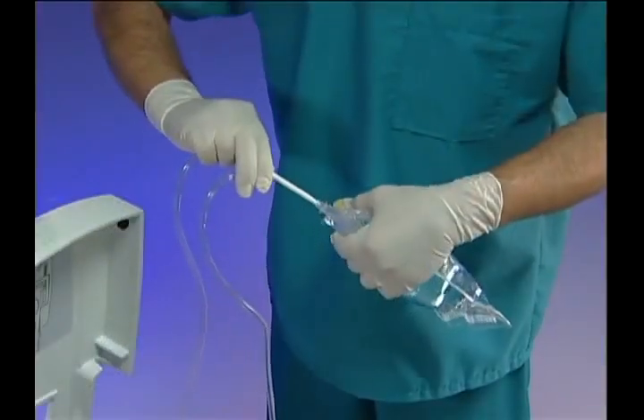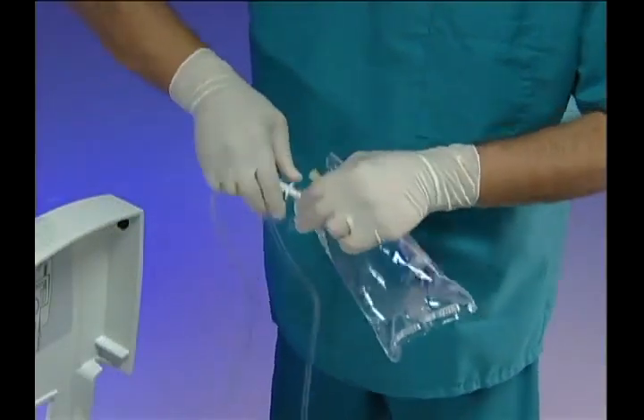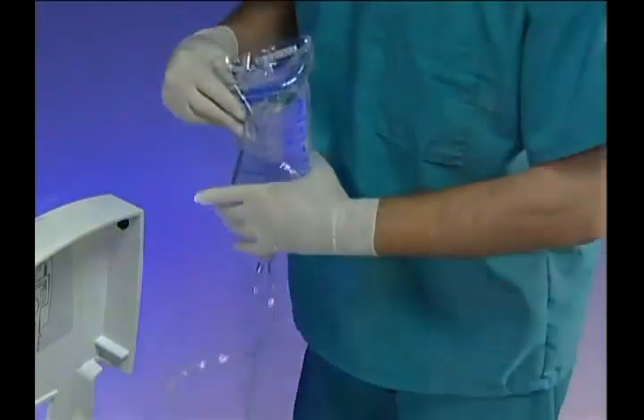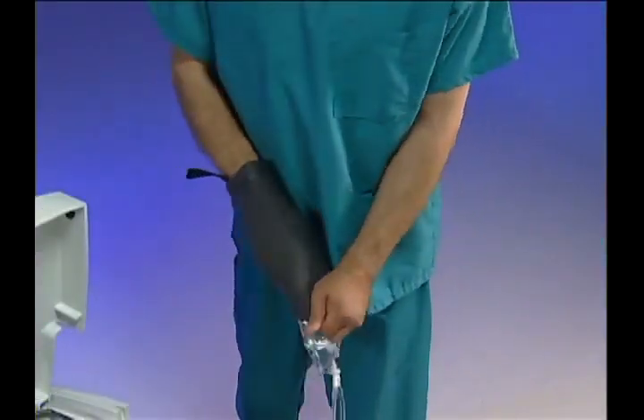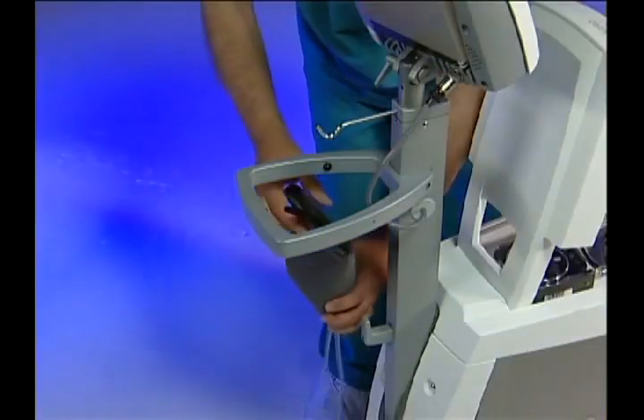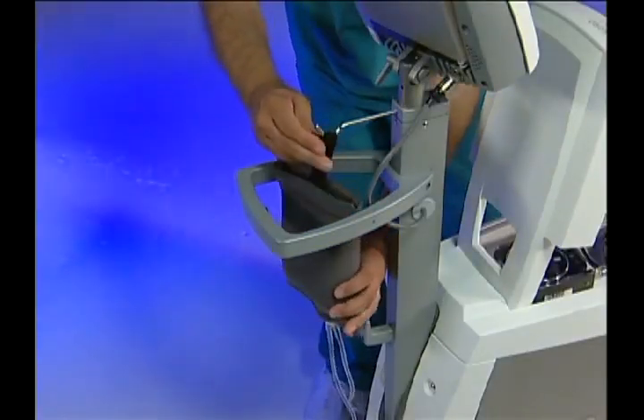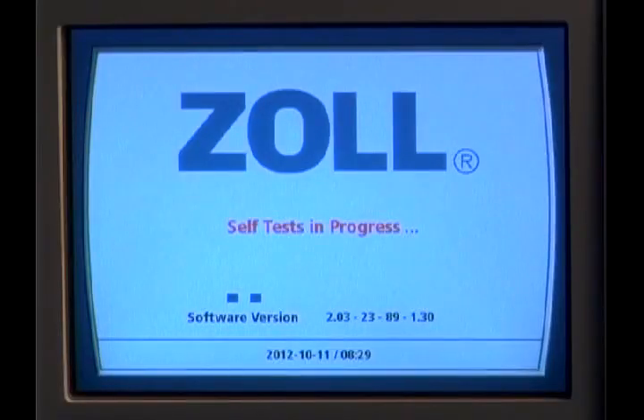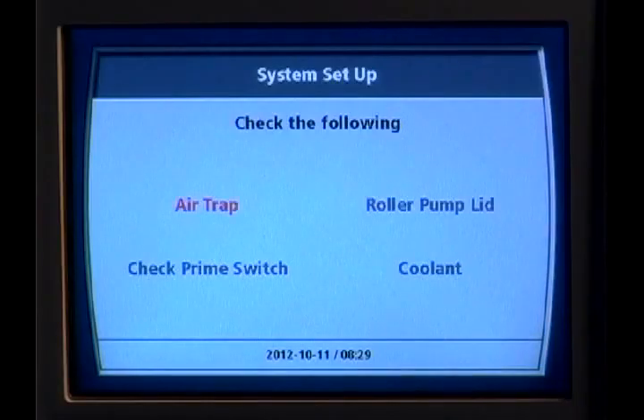Using aseptic technique, spike a 500 cc saline bag. Slip the insulating jacket over the saline bag and hang the bag on the hook. Then, wait for the system to complete its self-test prior to proceeding to the next step. The self-test is completed when the system displays a screen with the word Air Trap in red.